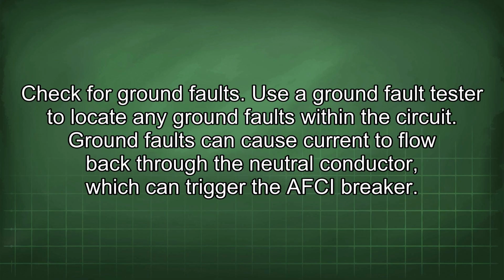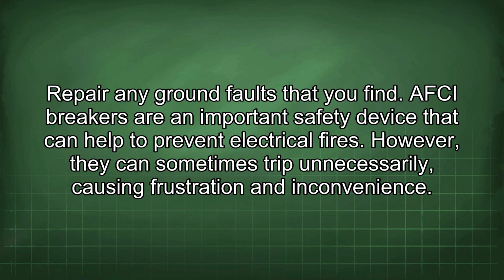Check for ground faults. Use a ground fault tester to locate any ground faults within the circuit. Ground faults can cause current to flow back through the neutral conductor, which can trigger the AFCI breaker. Repair any ground faults that you find.